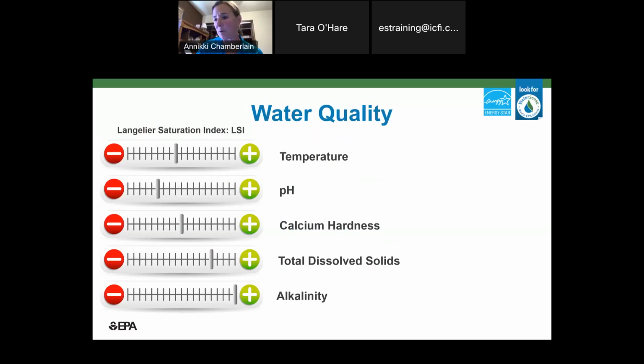Next, we go into water quality. We're not going to get too deep into this because we have more interesting things to talk about. But one thing to know is that water quality is incredibly important. A very common system for managing cooling tower water use is called the Langelier Saturation Index, the LSI. You'll probably see it on your reports. I like this as an example because it shows you that it's not just one water quality parameter. A lot of times we say, oh, we'll just test the conductivity. But it's all of these different parameters: temperature is a big one, pH, calcium hardness, dissolved solids, alkalinity. How do all these interact with each other? What are the different levels? That's what's going to tell us how to operate the tower.